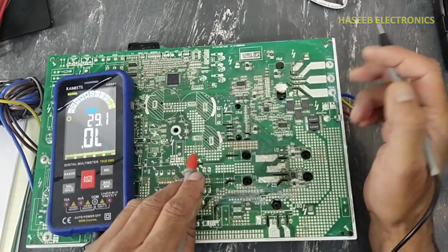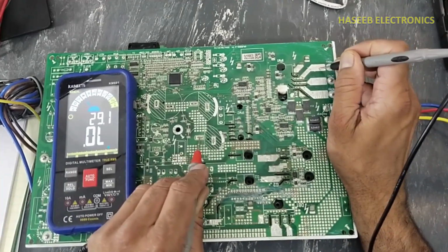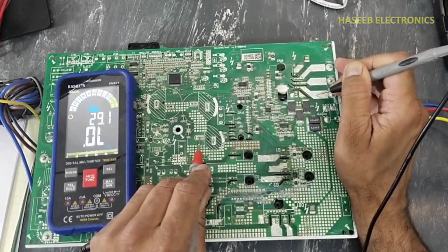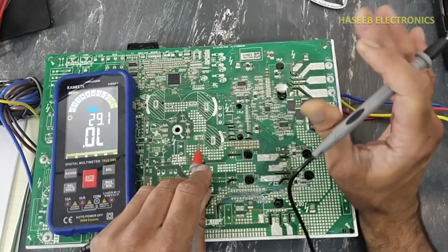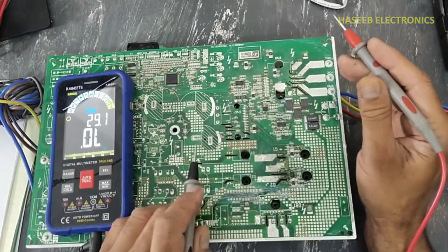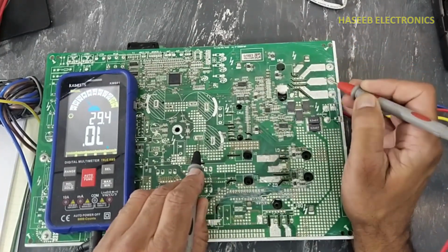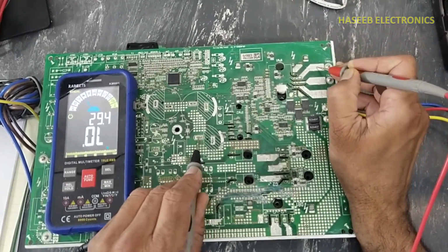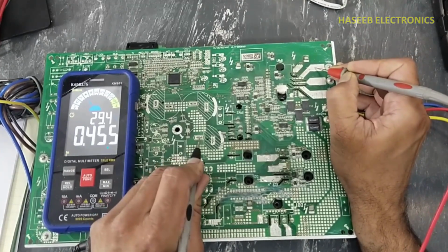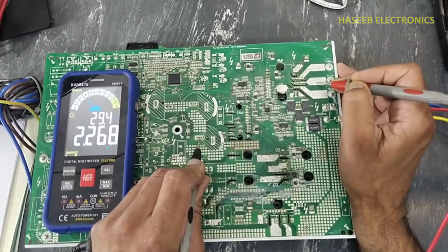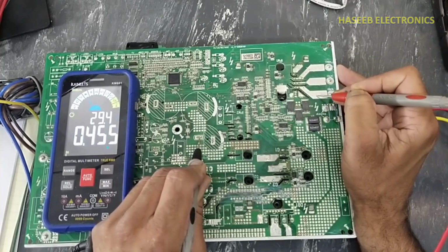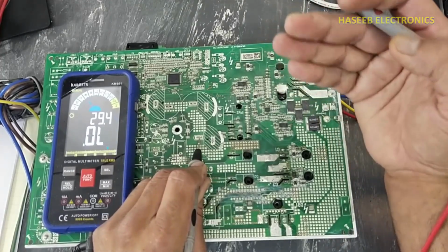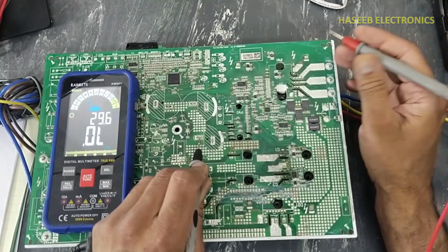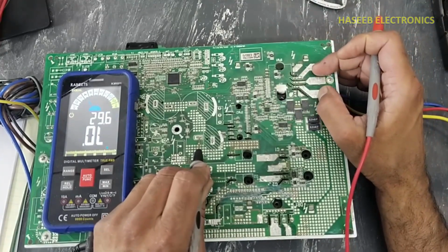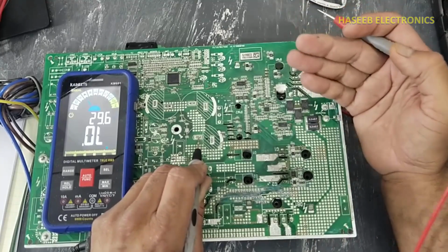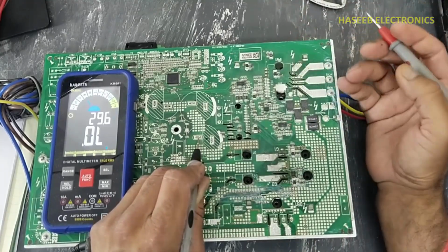Now connect the red lead at the positive terminal and check at UVW output leads. It is open. It is in good condition. Now black lead at the positive terminal and check here. 0.45, 0.45, 0.45. Now the high side 3 IGBT diodes are good. If we find short circuit or open, at that time the higher side IGBTs are not good.